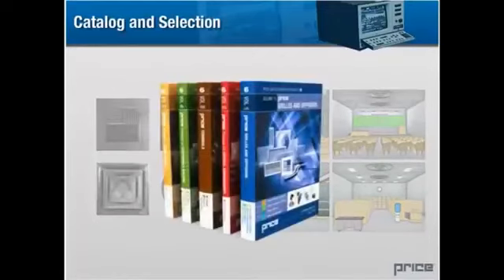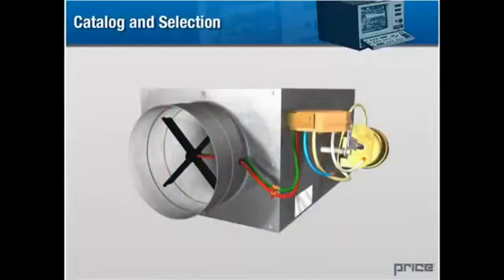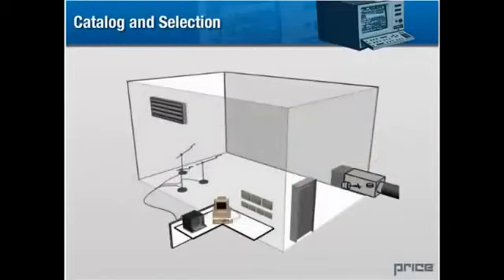Sound power data and NC ratings for most products are readily available in the price catalog. Let's take a look at how this information is presented and how we can use it to select products for a particular environment. As you may recall, we placed the device to be tested into the reverberant sound room. Sound data is presented differently in the catalog for GRDs and terminal units, so for this example, we will examine the discharge sound from a terminal unit.